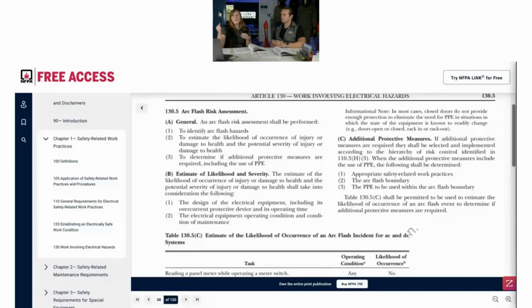Another situation would be those disconnect switches that just have that little hook that keeps the hinge door on. There have been times, yes, very technical terms here, a little hook, that an arc flash occurs and it pops the door open because that latch is not strong enough to keep that door shut in an arc flash situation, a faulting situation. Certainly, if you don't have all the panel cover screws in place and secured properly, even if it is arc rated equipment, that could cause the cover to come off. So it's just saying, be aware, just because it looks closed does not necessarily mean that it's going to contain the hazard in a faulting condition every time. Okay.